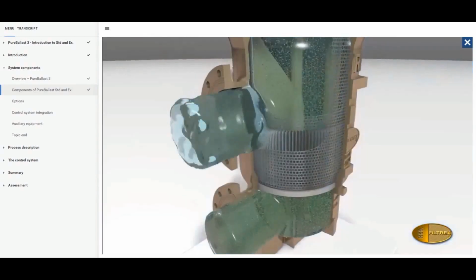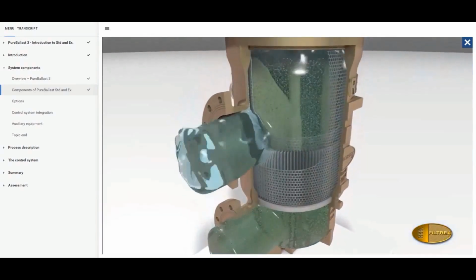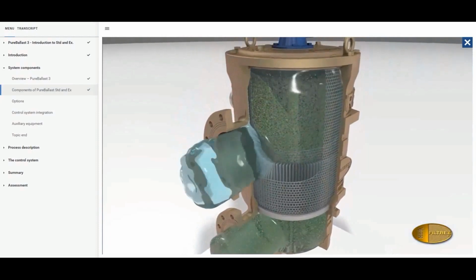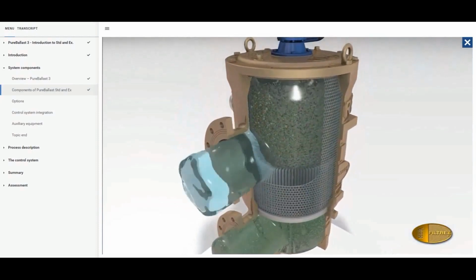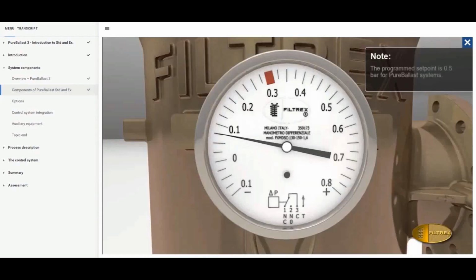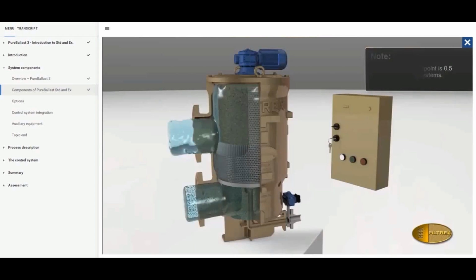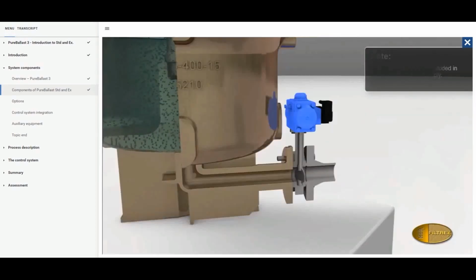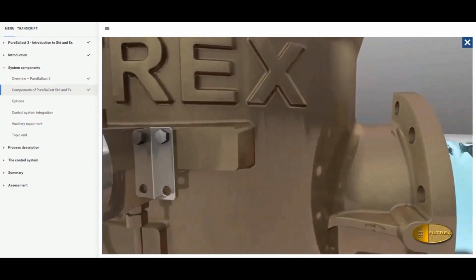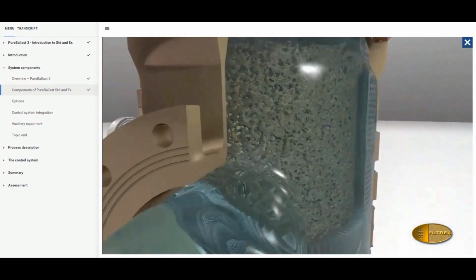As more and more impurities build up in the filtering element, the differential pressure gradually increases, as shown by the indicator, until the programmed set point is reached. Through the control panel, the electric motor is activated, then the backwash valve is opened, starting the rotation of the cleaning nozzle and the cleaning phase.